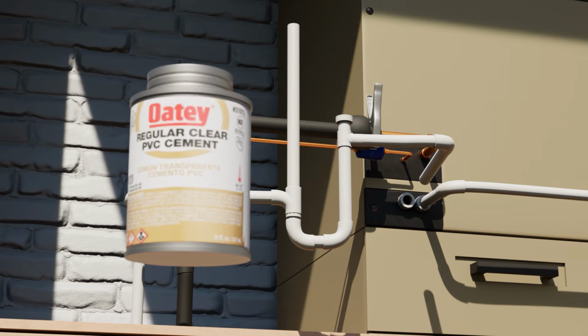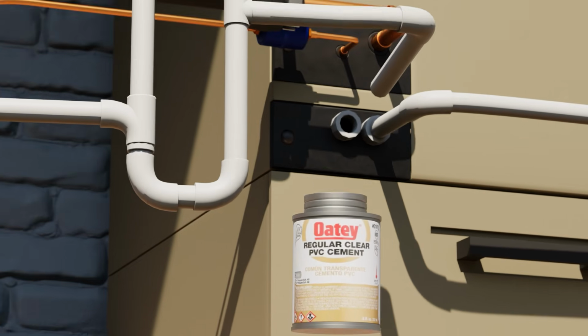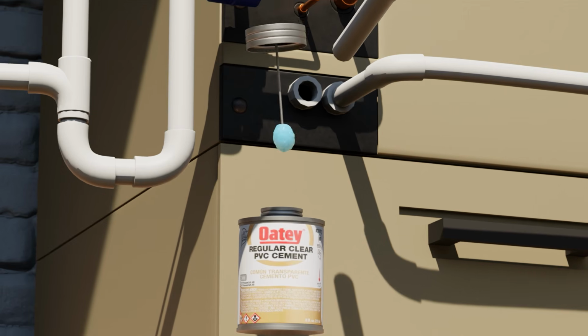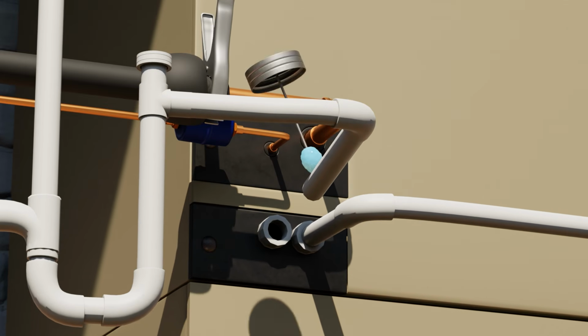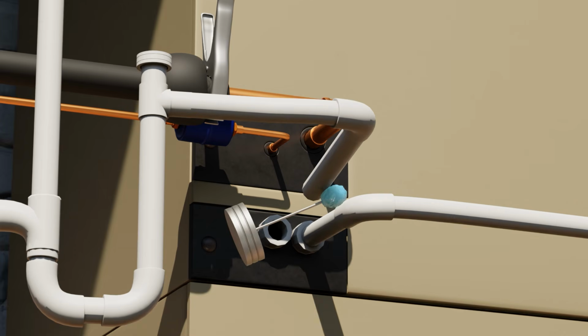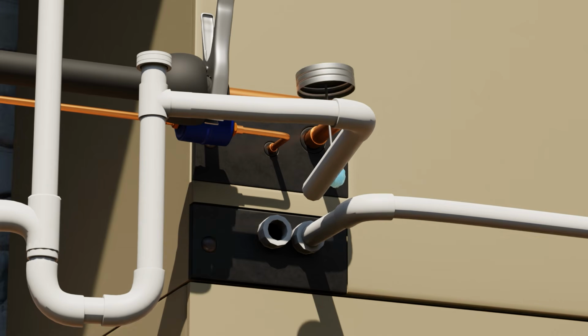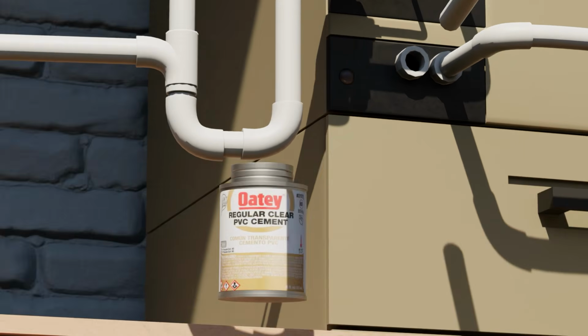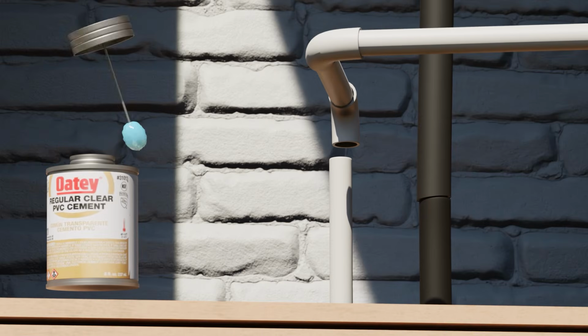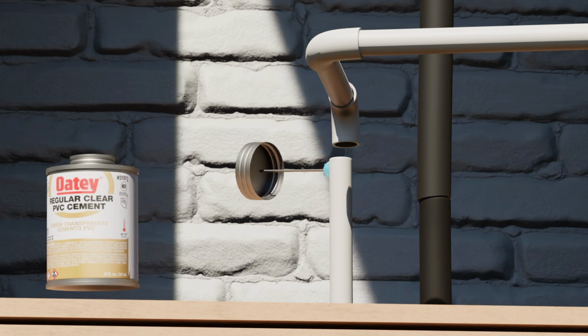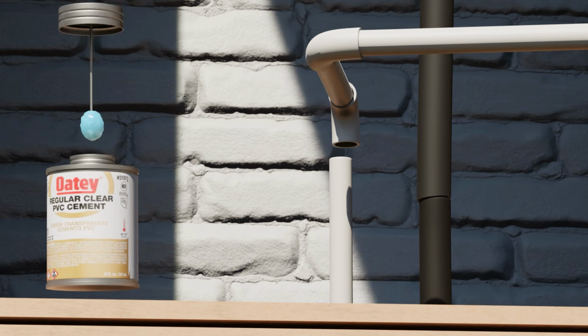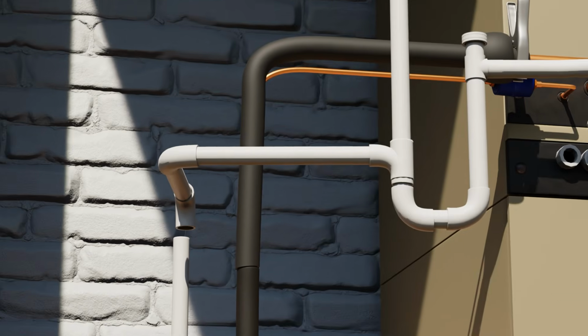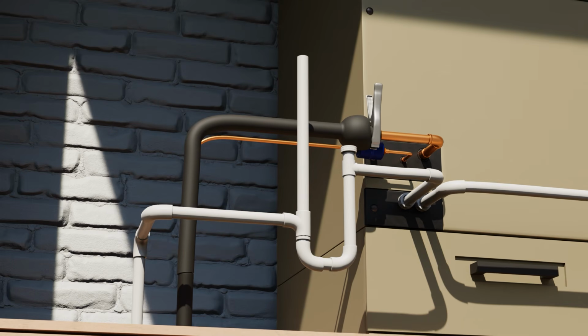When gluing PVC, apply glue to the male side of the connection and hold it in place. Whenever possible, give it a quarter turn once you insert it into place. Here, we're not showing using a primer. If it were a pressurized system, we would definitely use a primer. We find that as long as the PVC is clean, a regular medium cement works okay. I know this may be somewhat controversial, so if your company or your local authority having jurisdiction requires primer, then use primer prior to gluing.